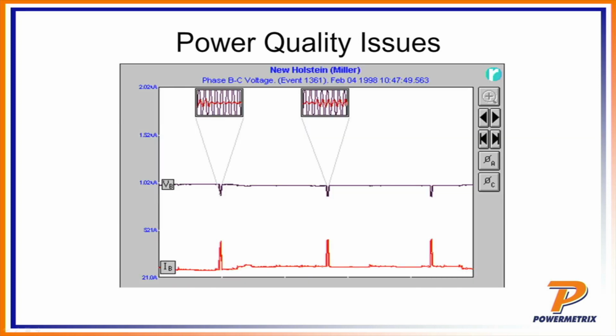Here's another example that was out at, I think, a milling plant. What you see here is that you've got a periodic waveform issue going on, and so we'll have a spike. You've got the voltage on the top, and you have the current on the bottom. And so periodically we will get a current spike, and that spike in current may be where a piece of equipment is switching into the system, or perhaps a switching power supply that's causing it to pull a large transient. And what you'll note is that the voltage will dip momentarily while there's that large surge in current. So once again, that's a regulation issue.